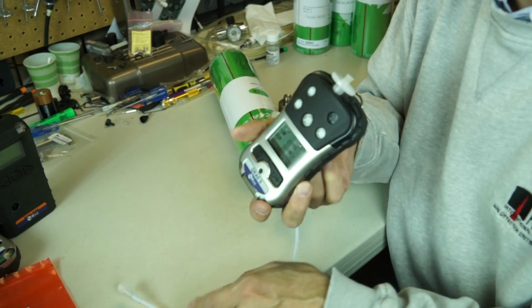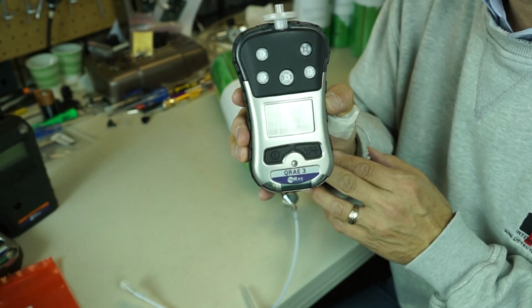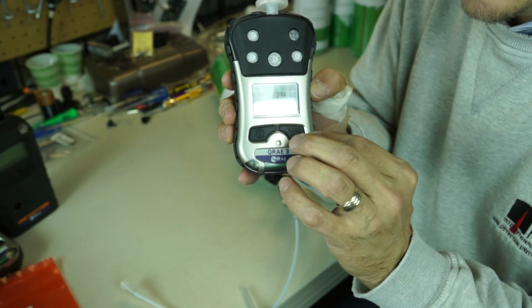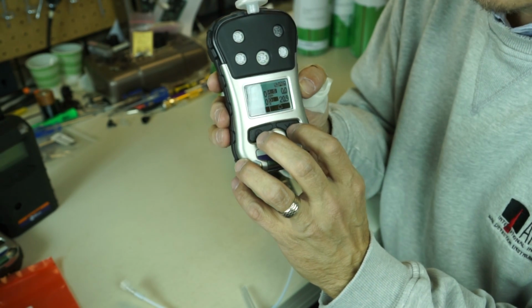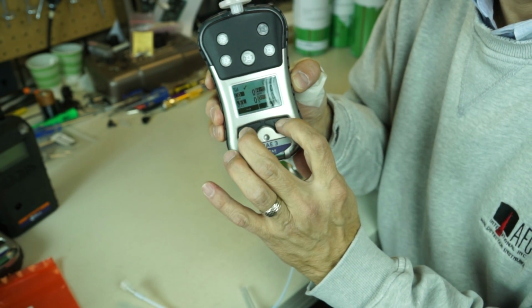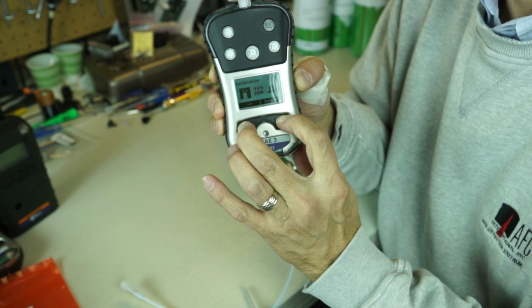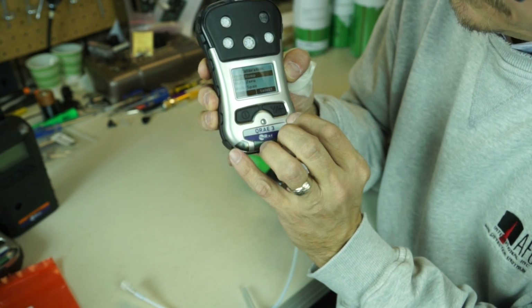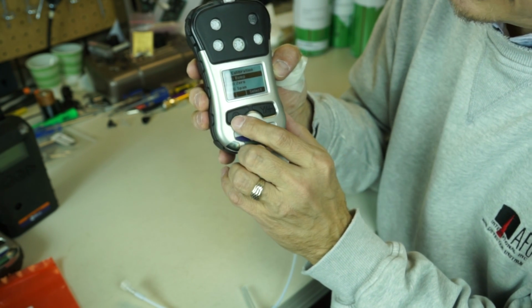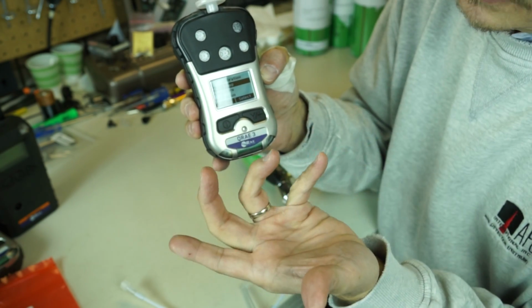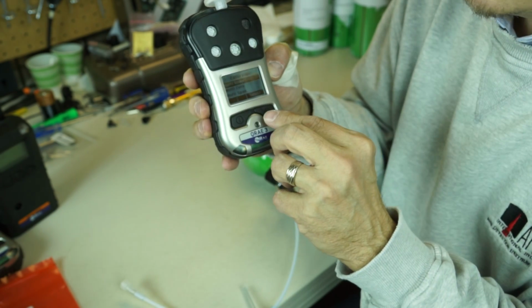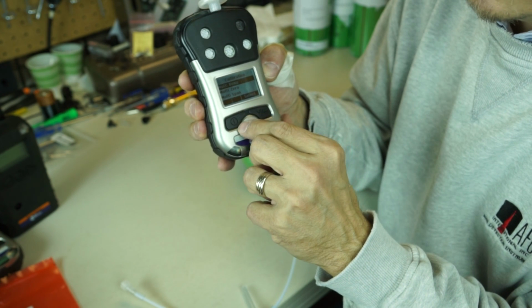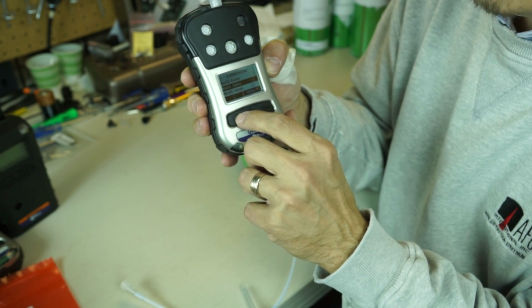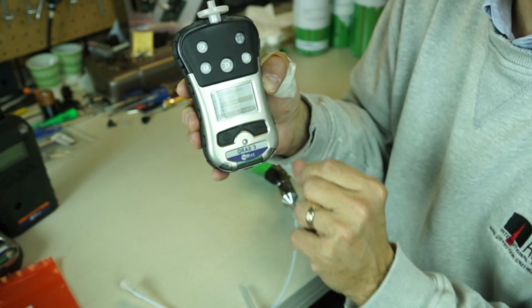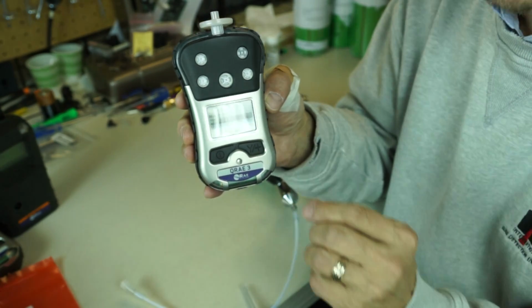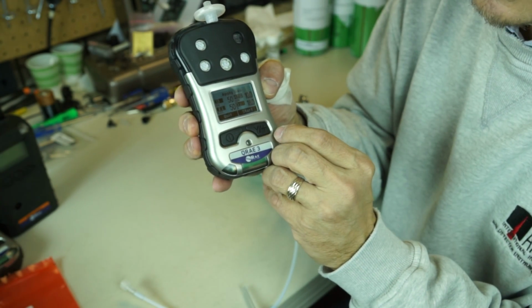Take my instrument, QRae 3, okay, and I'm going to go ahead and get into the calibration mode. On a Rae Systems, it's mode in no, or mode in yes in this case. And it's going to ask me for a password. Sometimes, if it's not password protected, you can go right into the calibration, and you'll scroll down till you see multi-span. Can you see that? Multi-span. I'm going to hit yes and select.